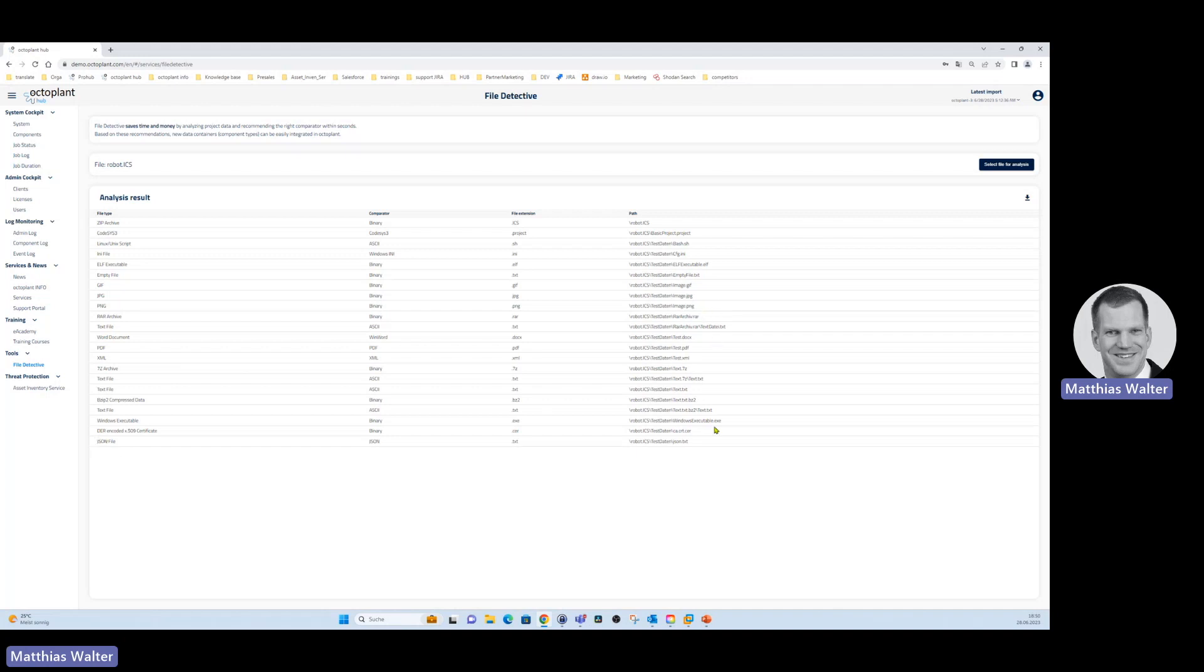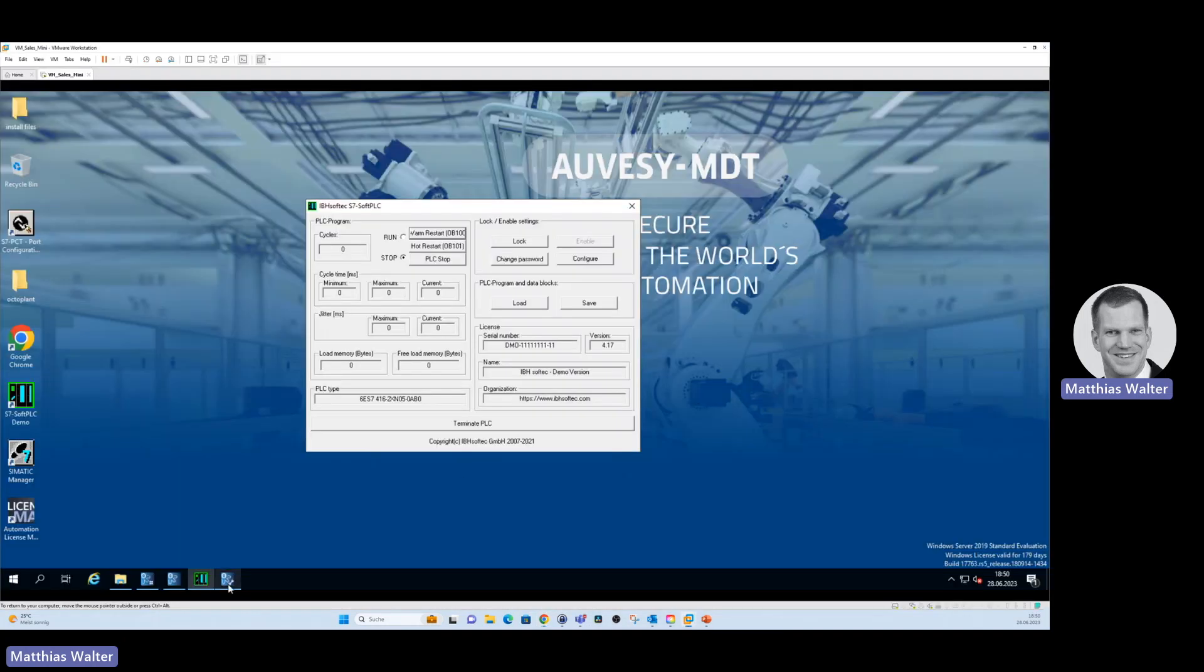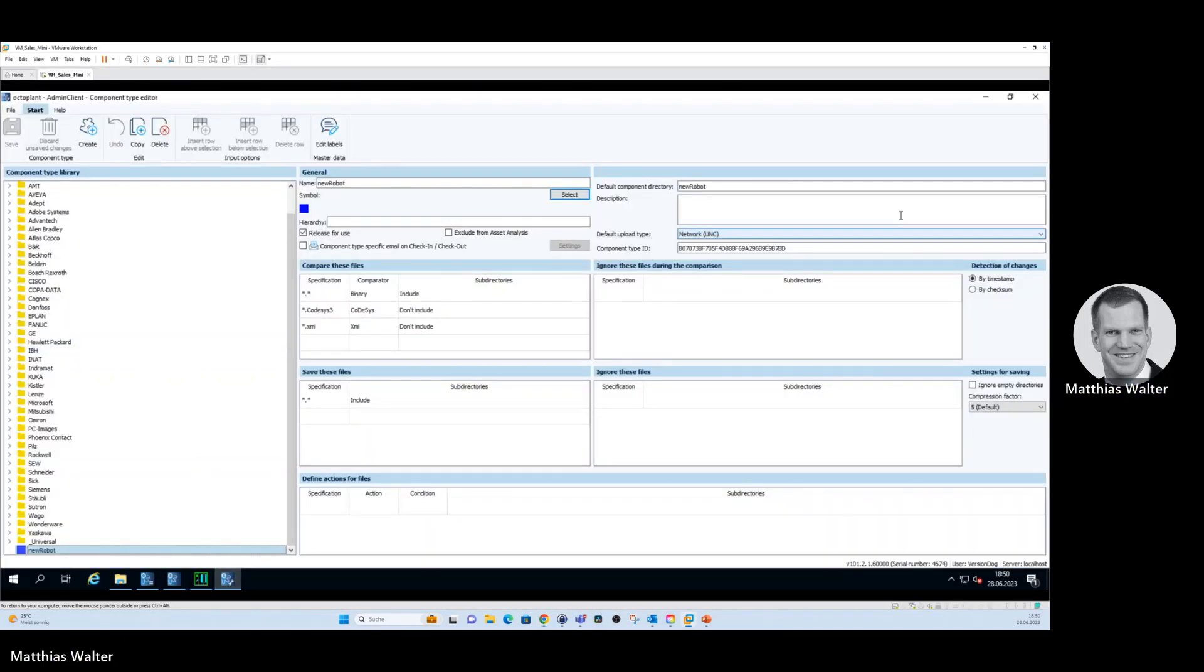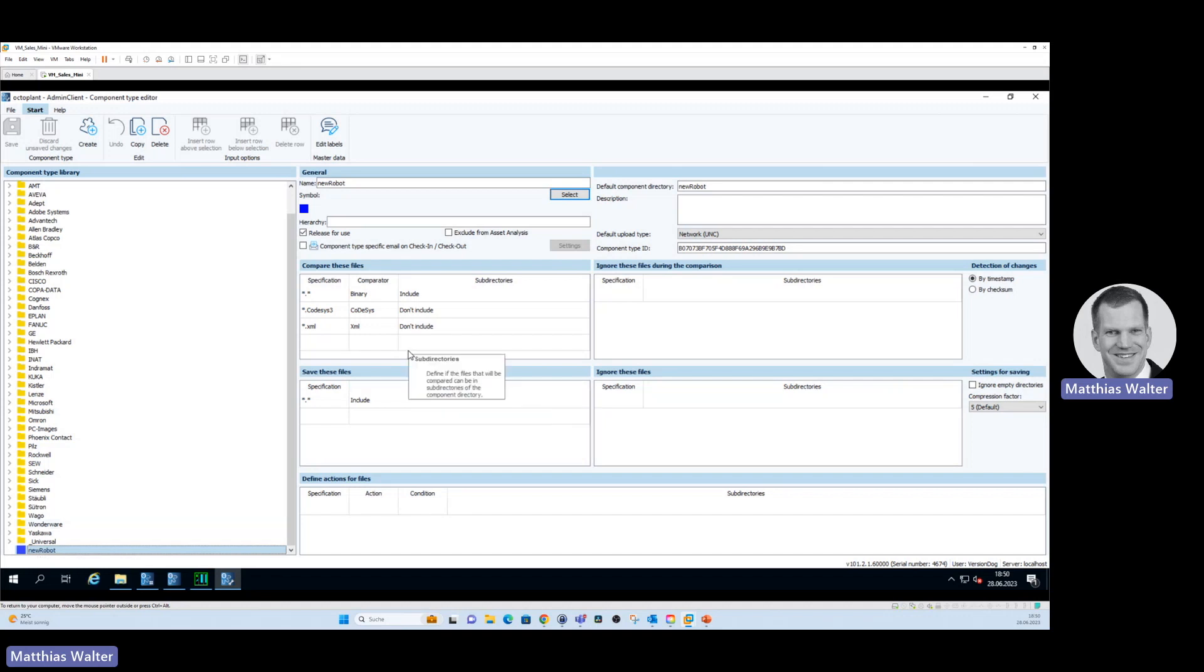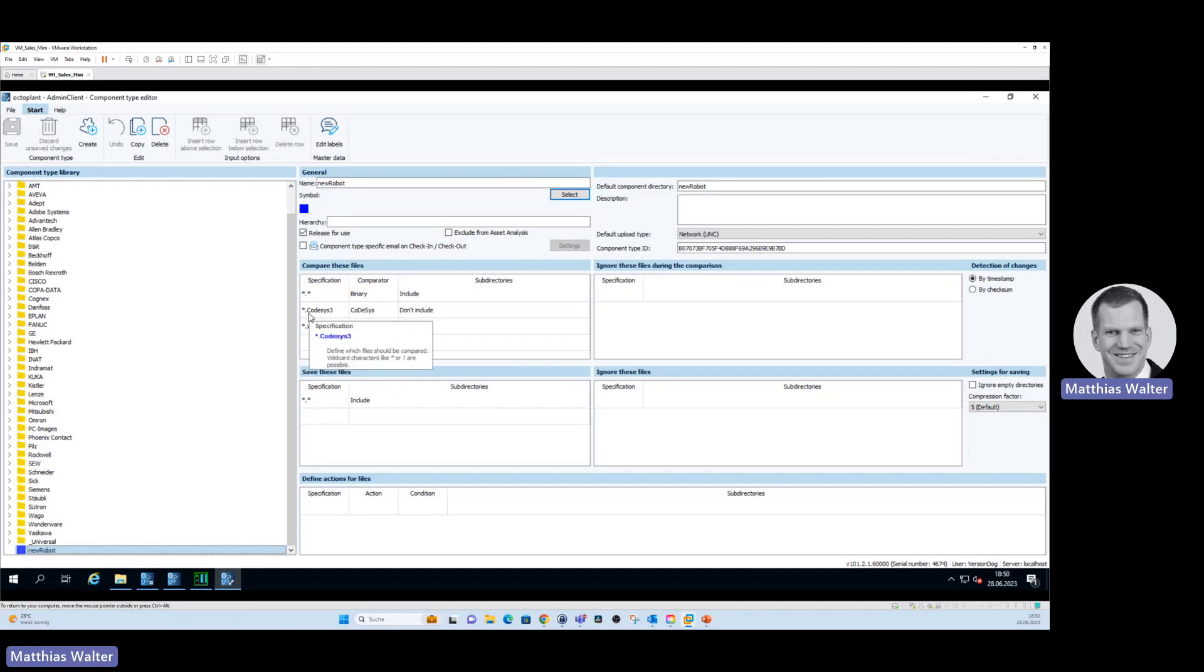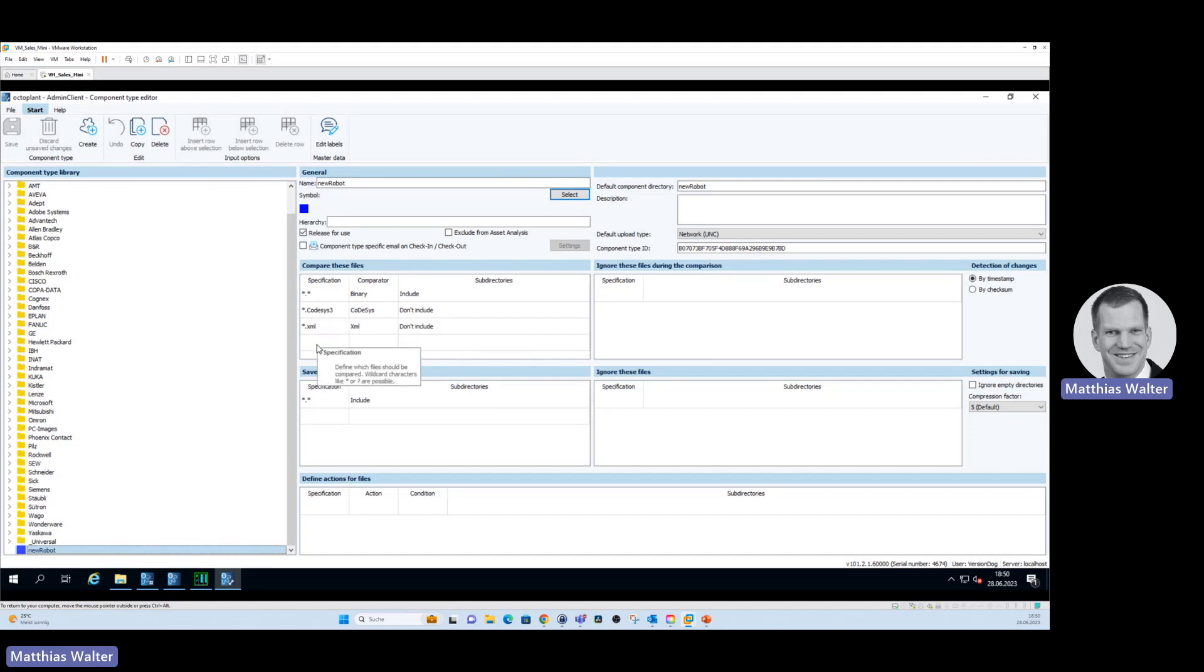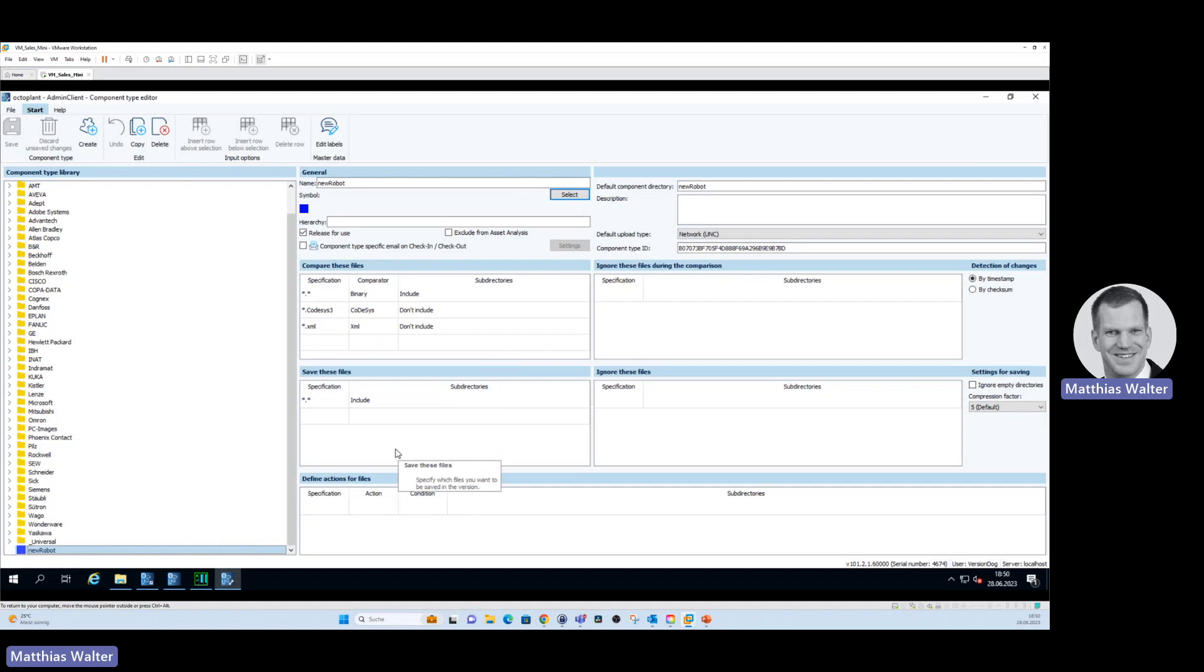This we have to configure. For doing so, we have to go to the admin client. In the admin client, we have to select component type editor. And here in the component type editor, you have to click create. I already created a new file type. This is called new robot. And here I basically just told OctoPlant to do exactly what the file detective suggested. Meaning that for a CODESYS file, use the comparator CODESYS. For an XML file, use the comparator XML and so on. And as simple as that and as fast as that, you create your own component type. And then you can basically also do backups and recovery with OctoPlant.